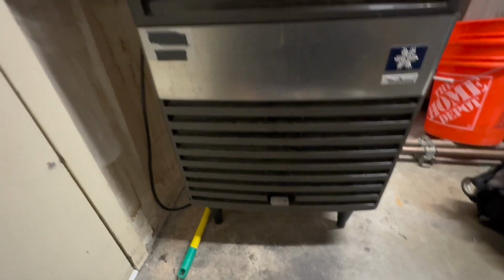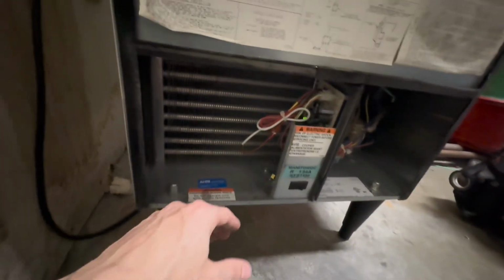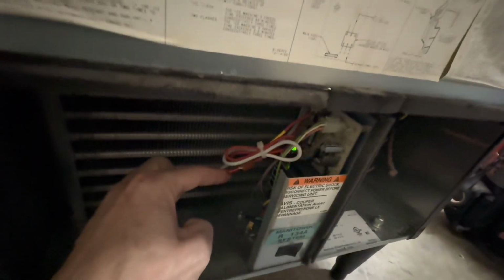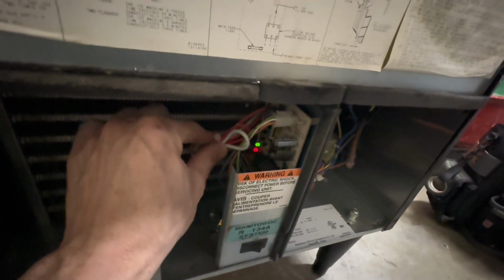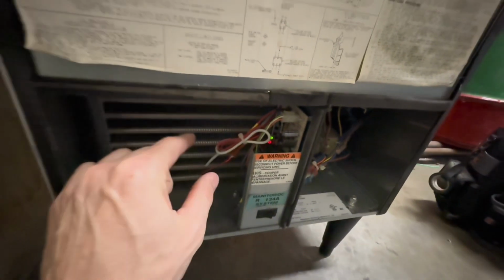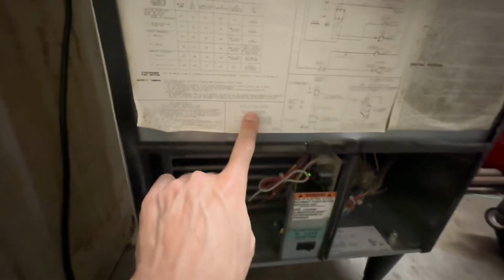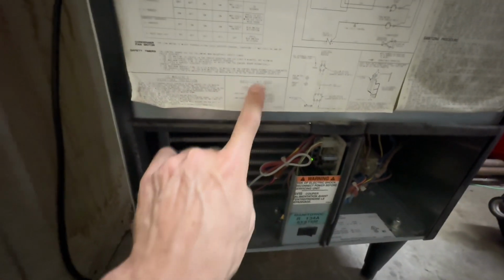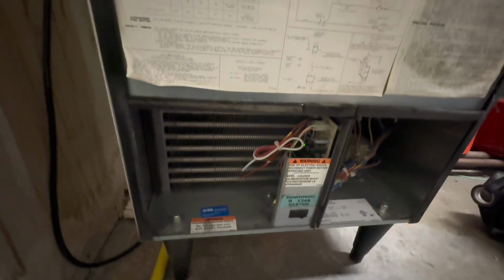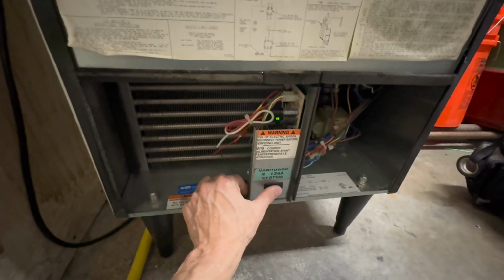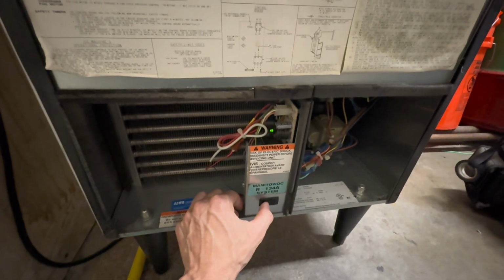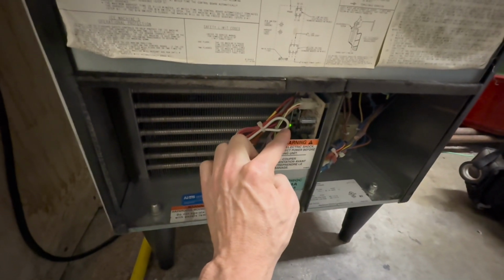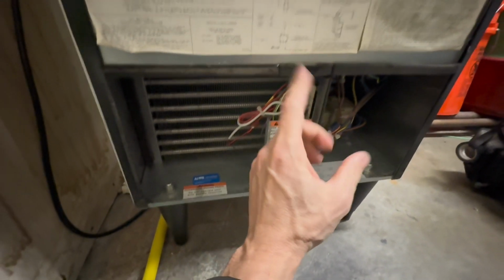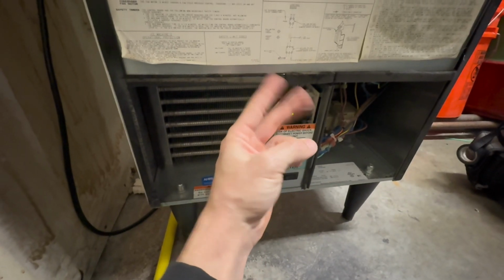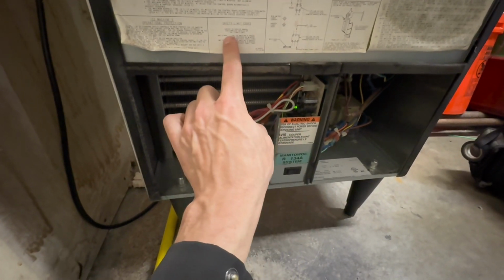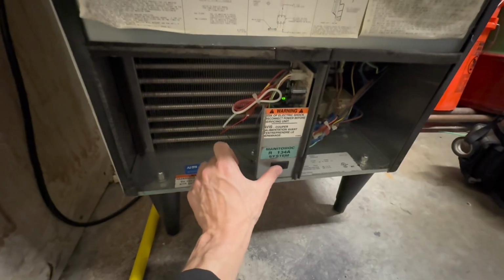My control board. Just removed my front panel, and on my control board there is a red light flashing. That red light indicates that the machine shut off on one of these two safety limit codes. Let me read over it and I'll tell you which one it is. So what I did was I clicked this to off, and then when I click it back on, the red LED, which is the harvest light, will flash either one time or two times, and that'll tell us which of the two errors shut the machine off.